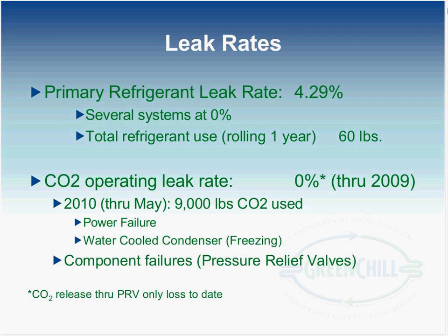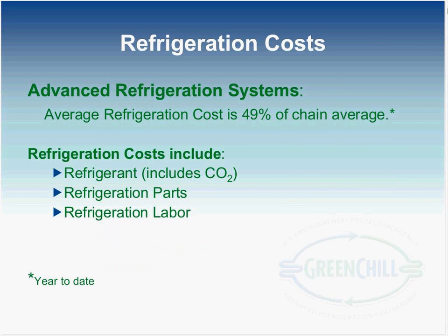One of the things we are seeing is that on some of the components, specifically the pressure relief valve, we've seen 1 or 2 failures from the manufacturer of the pressure relief valve, so we've had to replace that valve. And in that sense, I guess it would be a leak, but because of the dynamics of CO2 itself, it doesn't release itself all at one time, so we're able to capture those fairly quickly, but I want to have a call out on our leak rates.